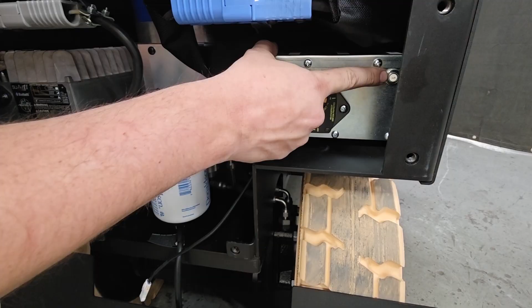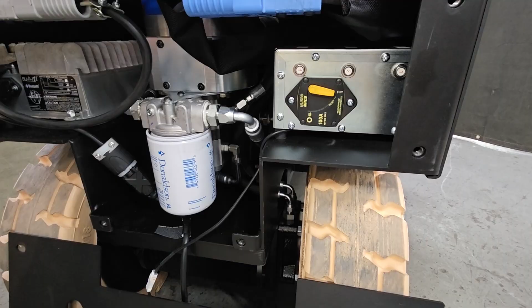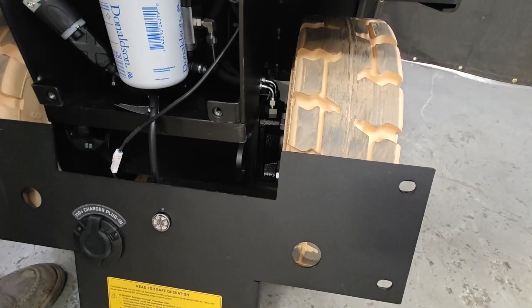In addition to the main circuit breaker, there are 3 smaller circuits that have resettable breakers as well. The main control circuit is reset with this 1 amp breaker on the far side of the controller, and then the other smaller control circuits are protected here as well. Make sure that all 3 of these are in there fully in position before testing any further. If you see that this main breaker is tripped, you can reset it through the access hole in the back panel.